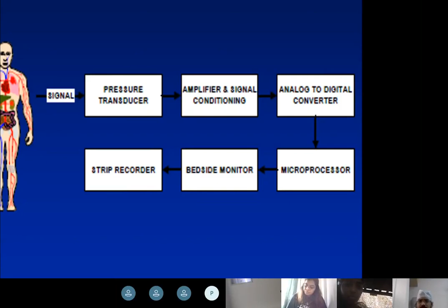This small thing that you're seeing over there, this small blue gadget that you attach to the hand, is called a transducer. On the volume view, there are two kinds of transducer. If you see, there is one gray color transducer which is attached, and there is another usual transducer that you attach. Okay, so what does this do? It converts the mechanical impulse of a pressure wave into an electrical signal through a movement of a strain gauge. I'll explain to you what this is all about.